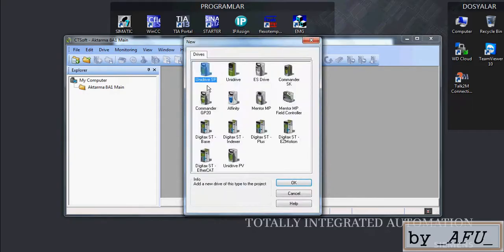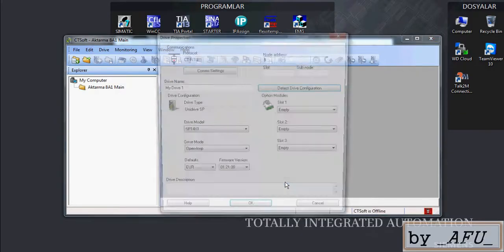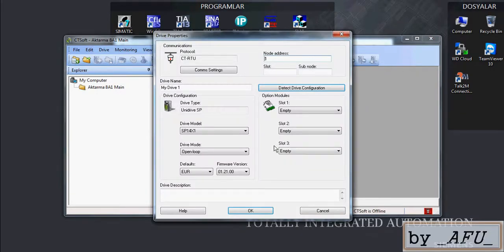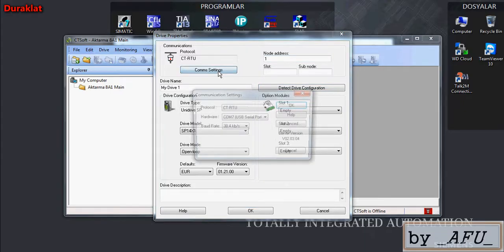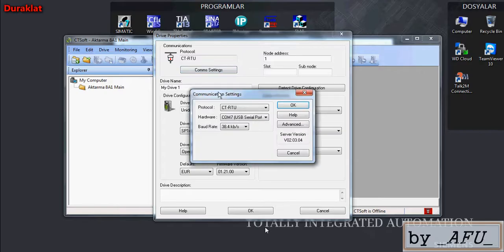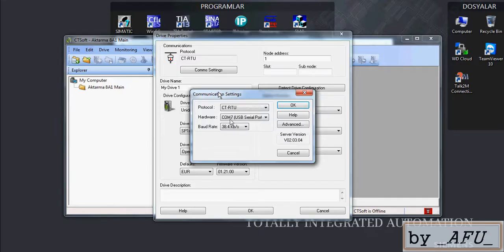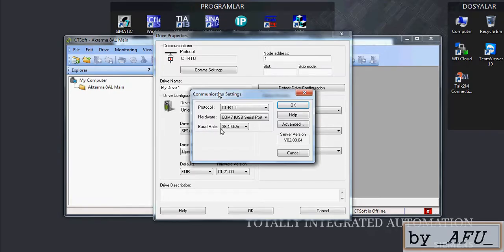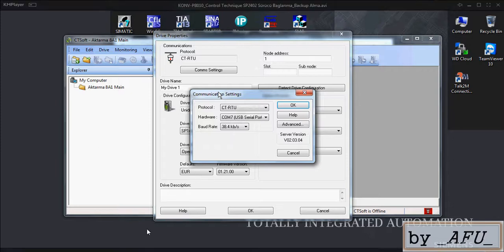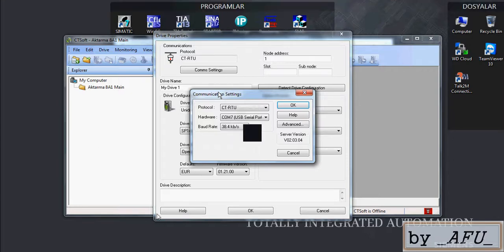Okay, and you select the drive model. Drive model is Unidrive SP. And there is communication settings here. For communication settings you need COM port number, you have to find it in your device manager for the USB cable. And baud rate also you need, and node address in the manual.